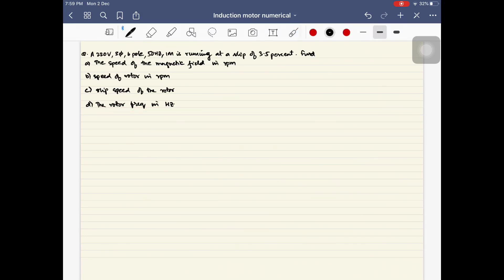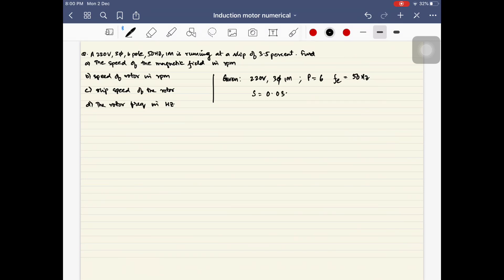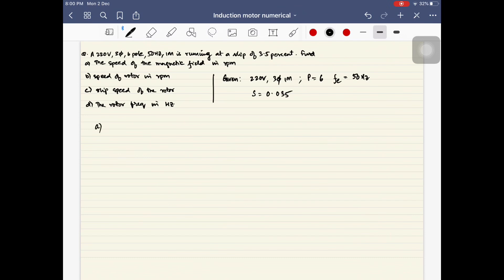As in all numericals, we first write down what is given. The given quantities are: it is a 220-volt three-phase induction motor, number of poles p = 6, frequency f_electrical = 50 hertz, and slip = 3.5%, that is s = 0.035. For part (a), the speed of the magnetic field is the synchronous speed n_s, given by n_s = 120 × f_electrical / p = 120 × 50 / 6 = 1000 rpm.